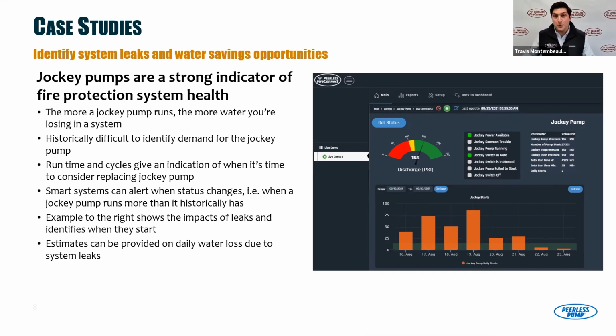So if I break an elbow or a pipe bursts, or usually if a sprinkler head opens, it's enough of a pressure drop for your fire pump to open. But with some type of significant drop in the system where you're losing a lot of water, you'll start to see more frequent jockey pump starts. That jockey pump over time will turn on more frequently and may run for longer periods of time. And that gives you an indicator that there's a problem. So by monitoring your jockey pump system, FireConnect is actually monitoring the overall health of your system as well here.